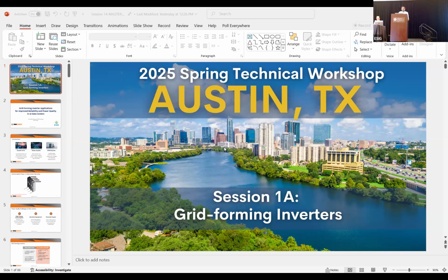In Tesla grid forming or Megapack, the grid forming operates as a standalone voltage and frequency source, which contains 2 main paths: the power dispatcher and the virtual machine. In the power dispatcher path, you can set the real and reactive power set points from a Tesla site controller, which is equivalent to a power plant controller. And the virtual machine path, which operates as a rotating machine, is a voltage source behind an impedance which responds to the voltage and frequency references received from the power plant controller. This is done through exciter models and swing equation models similar to those of a synchronous machine.